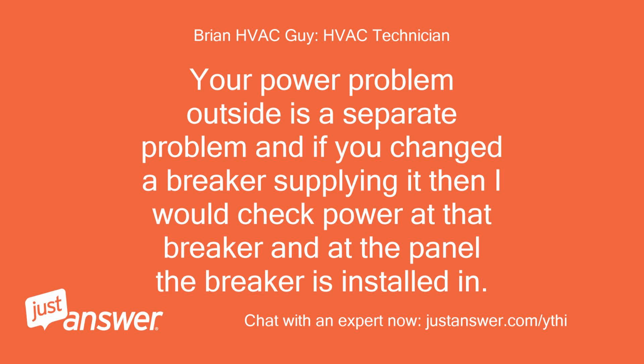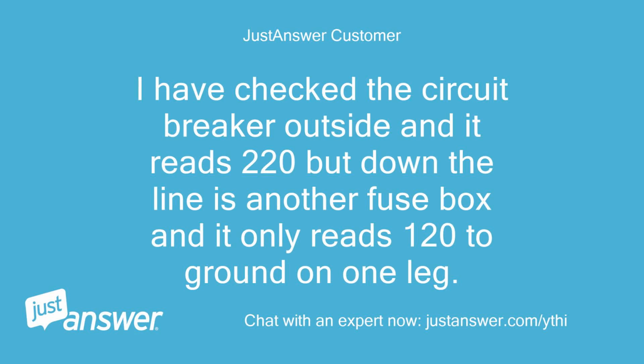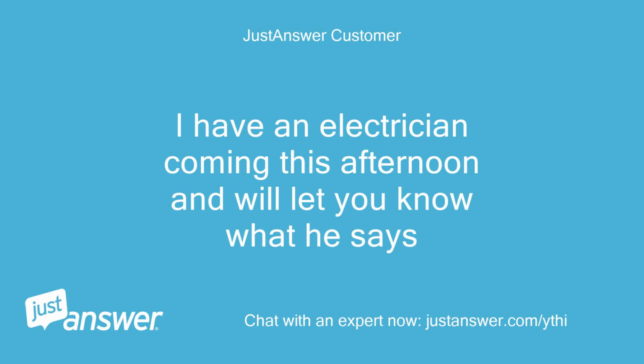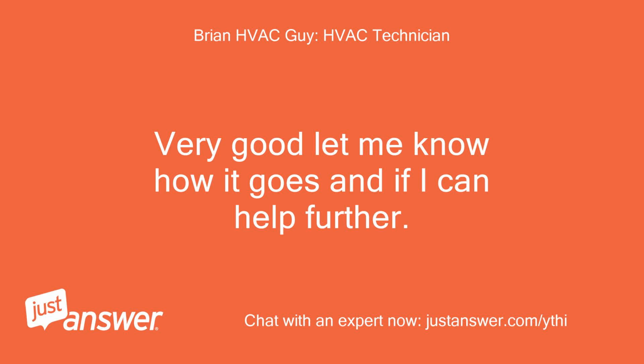Your power problem outside is a separate problem, and if you change the breaker supplying it, then I would check power at that breaker and at the panel the breaker is installed in. I have checked the circuit breaker outside and it reads 220, but down the line is another fuse box and it only reads 120 to ground on one leg. I have an electrician coming this afternoon and will let you know what he says. Very good, let me know how it goes and if I can help further.